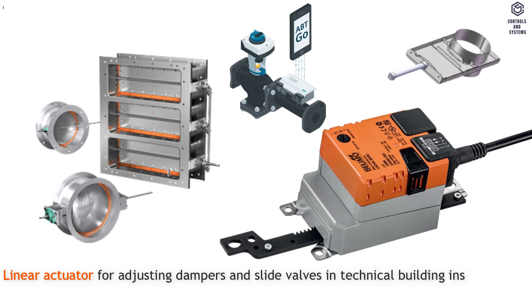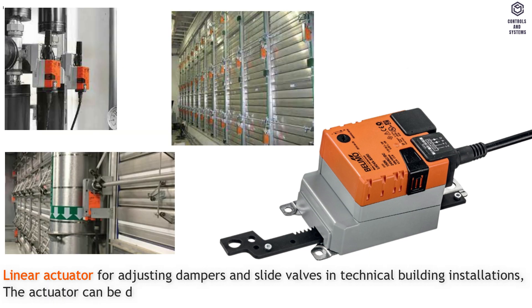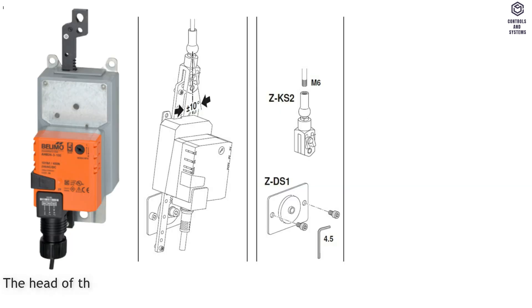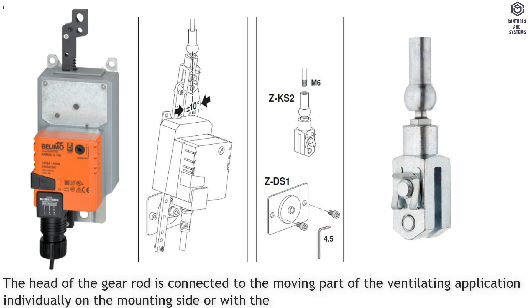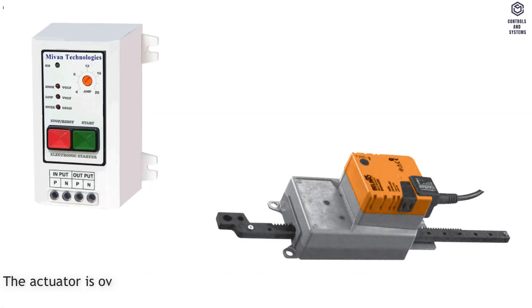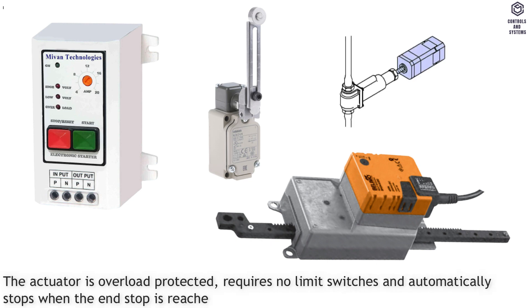Device Overview: this is a linear actuator for adjusting dampers and slide valves in technical building installations. The actuator can be directly connected with the application using the enclosed screws. The head of the gear rod is connected to the moving part of the ventilating application individually on the mounting side or with the Z-KS2 coupling piece provided. The actuator is overload protected, requires no limit switches, and automatically stops when the end stop is reached.